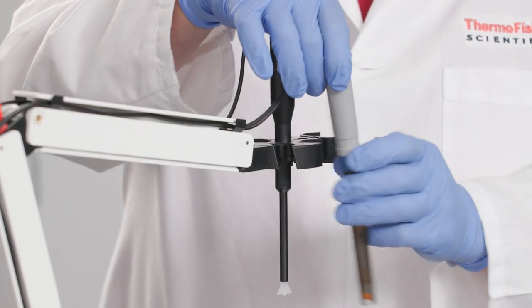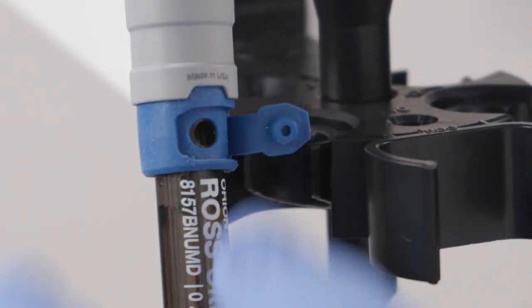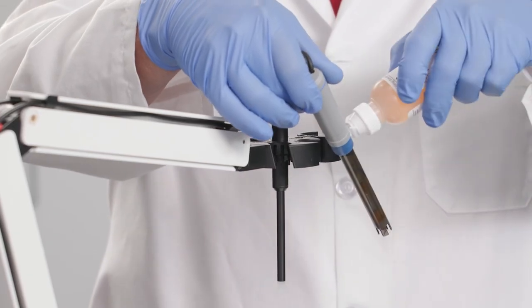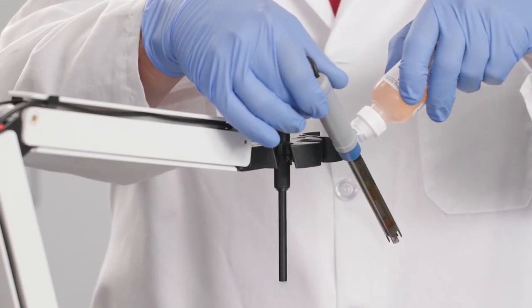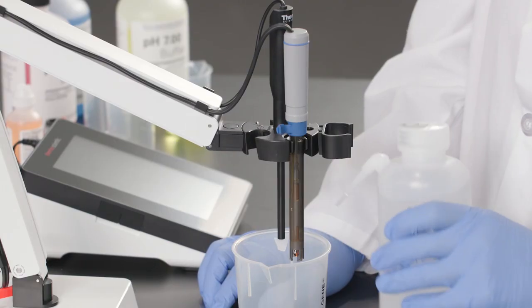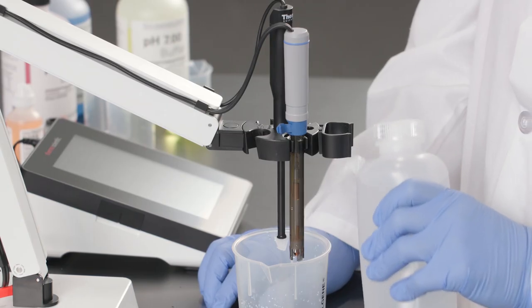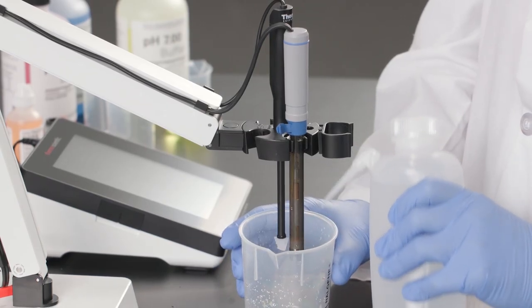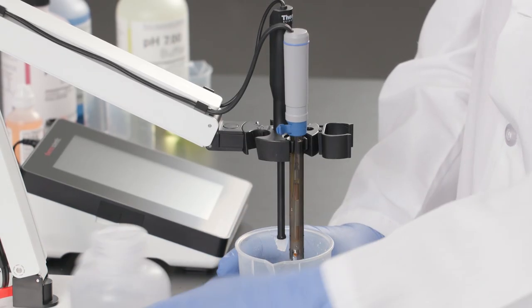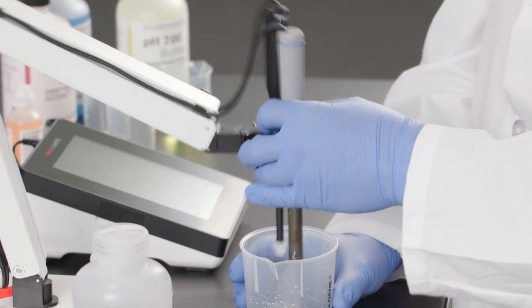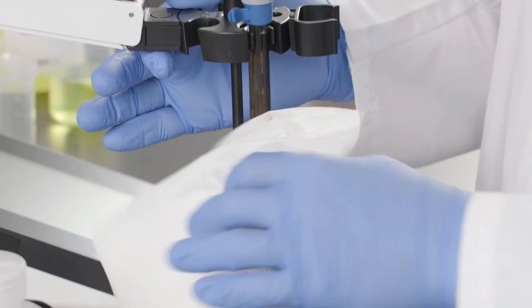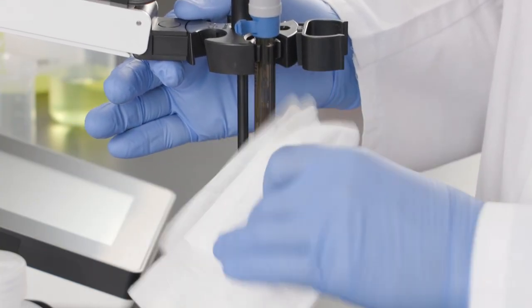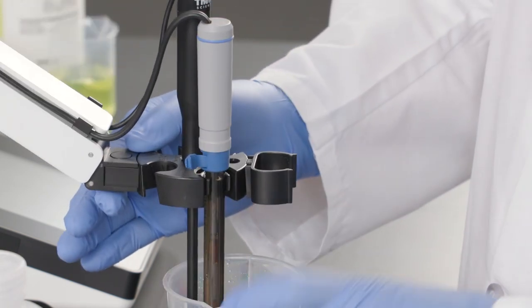If you're using a refillable electrode, as we are here, open the fill hole and top off the fill solution. This helps to ensure proper flow of the electrolyte solution. Rinse the electrode and the stirrer probe with purified water from the wash bottle. Gently shake the electrode holder to remove excess water droplets. If desired, blot briefly and gently with a laboratory wipe to remove excess water.